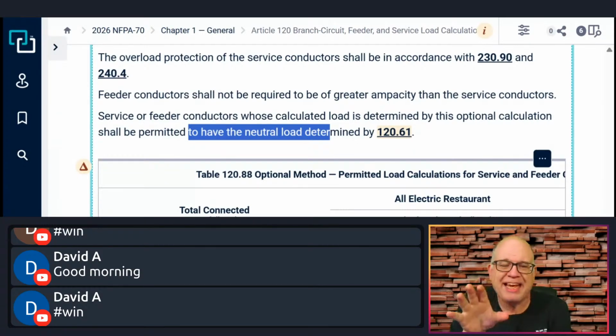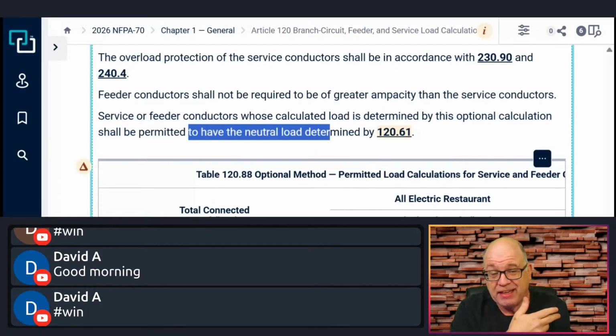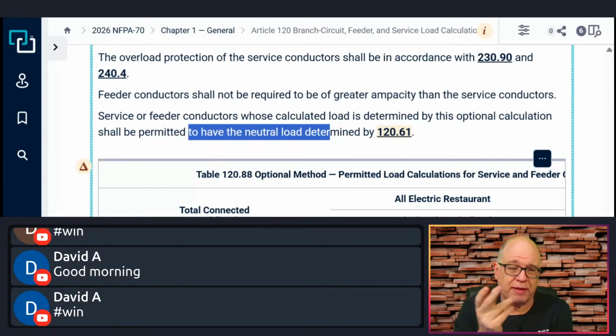So in order to get over into part 3, since I'm working in part 4, I have to have something that gets me over into part 3 to use the neutral calculation, okay? So in that scenario, you're going to have to calculate all of the loads. You're not going to be able to use the optional method in order to size the neutral, okay? Because you need to know what all those neutral loads are.